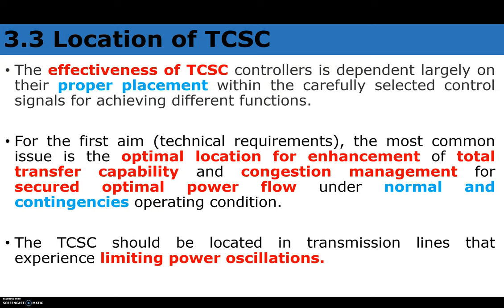Voltage swing will occur if the location is not properly chosen. So the location has to be carefully designed. We have to consider at what locations we can connect this device and what its effect will be. Before installation we have to carry out analysis and then decide the location — particularly where power oscillations will be least, since TCSC can also damp power swings and oscillations.